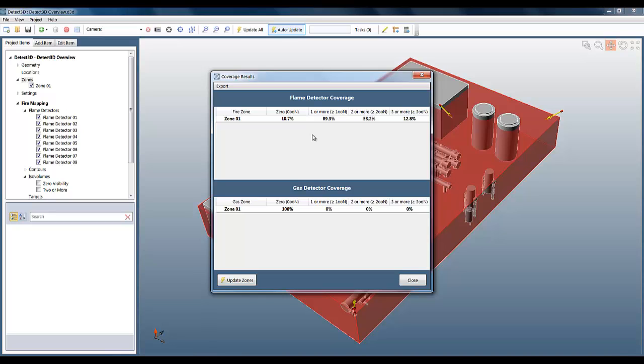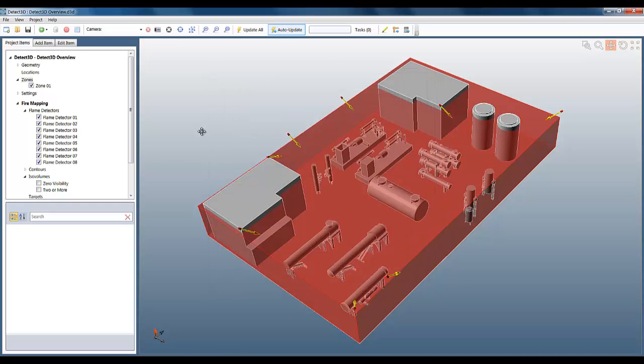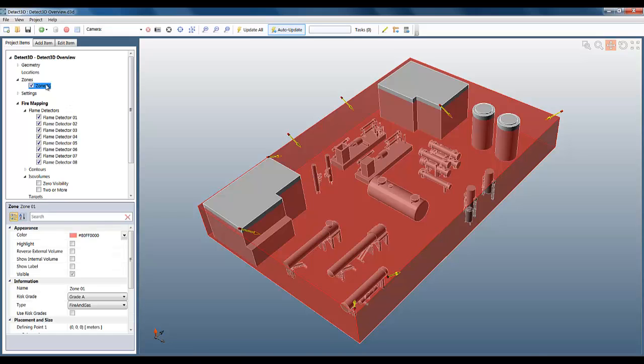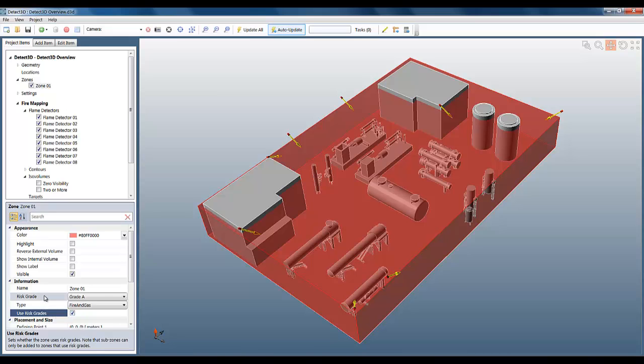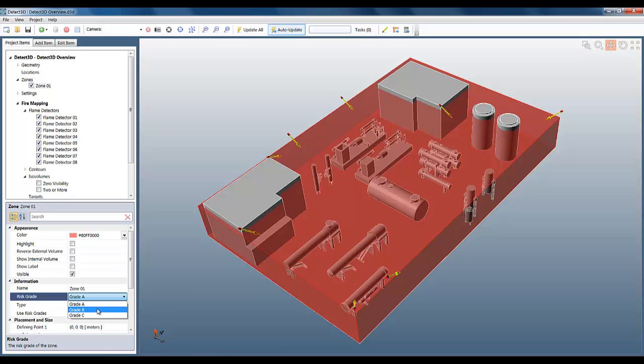These statistics are for the fire zone as a whole, but there may be areas in the fire zone that have a different risk category than the zone itself. We can define multiple subzones to mark out these different risk areas. To do this, I'm going to activate risk zones on the fire zone and select risk grade B. You can see that there are three preset risk categories and you can change the names of these to whatever you like in the software, but for now I'm going to keep it simple and stick with the preset A, B, C.